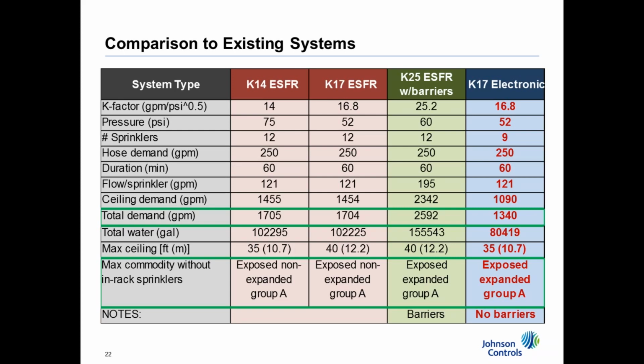And here's the real advantage I found dealing with some owners and some applications. If you look even at a K14 sprinkler, the K14 on the far left side, an older K14 sprinkler required roughly 1,455 gallons of water demand if you calculated the 4 heads on 3 lines as required by NFPA. If you use electronics, you're only going to use 1,090 gallons, and you're going to use it all efficiently.